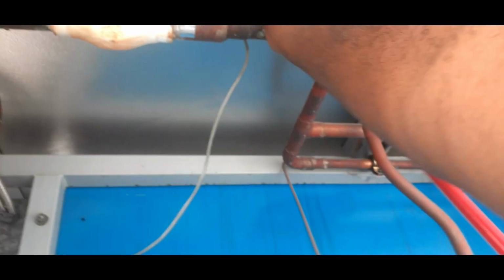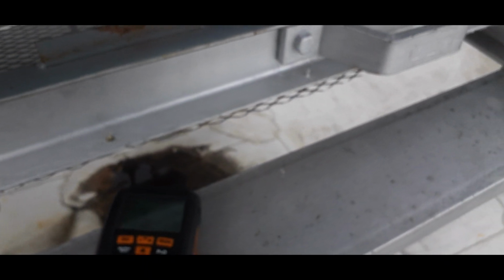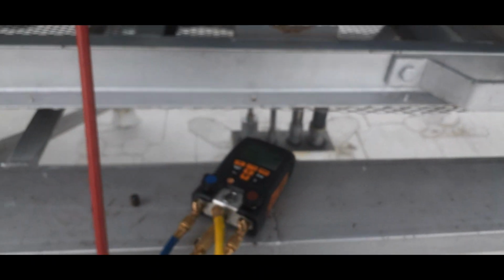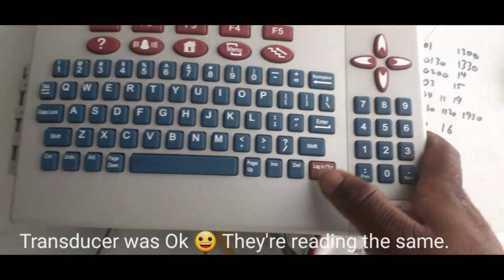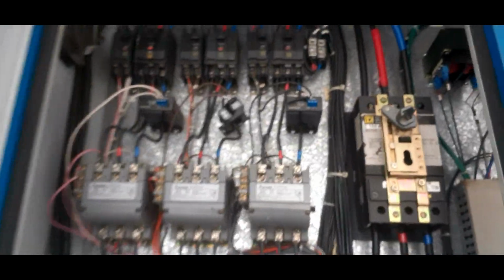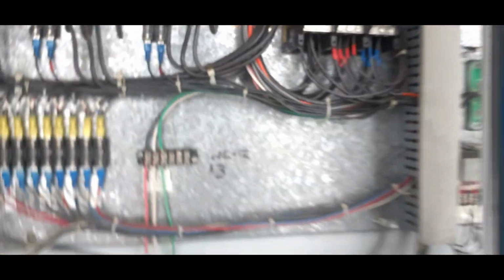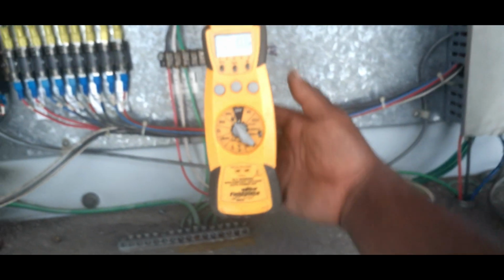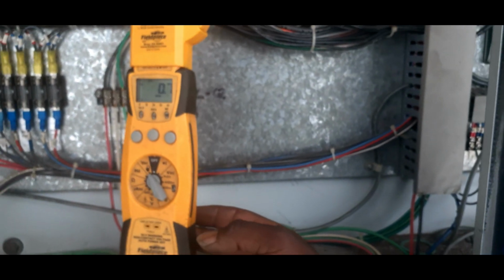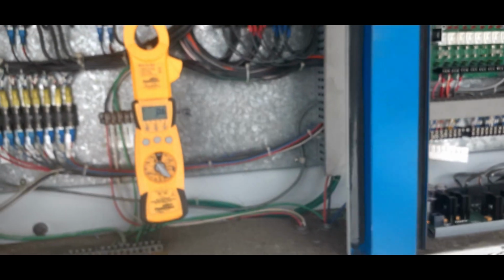I use the high side. It's not gonna break anything, but look at that, 113, 114. Just walk around, see what we got. 113. Anything trip? Compressor 2 is not running. Check our amp. 19 amp. That says 0 amp. I don't think that compressor is working.